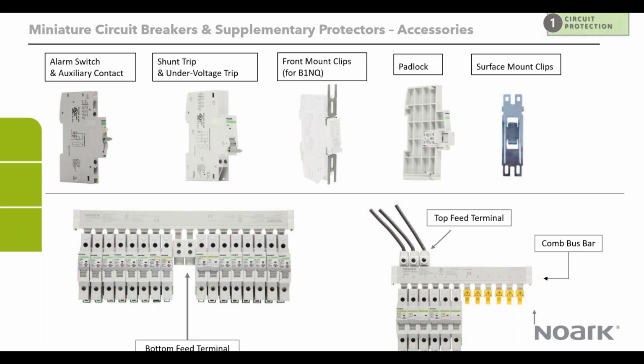In terms of the accessories, we've got all of these accessories available. I mentioned earlier, as part of your selection parameters, checking to be sure that the circuit breaker you're buying has the ability to use accessories. So you've got all these electrical and mechanical accessories: auxiliary and alarm switch, the shunt and undervoltage, the front mount clips, the padlock, surface mount. Also, we've got the bus bar system for the circuit breaker. This basically eliminates the need to do a huge amount of wiring, because you can just use a bus bar, and this gives you a plug and play kind of device, and it allows a quicker installation for the circuit breaker.